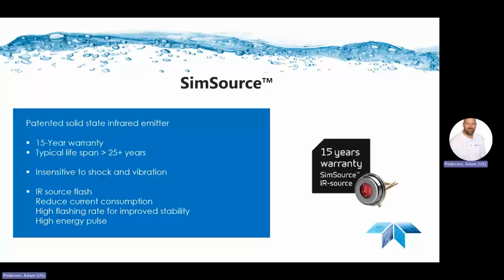The patented SimSource solid-state IR light source is extremely stable. The intensity of the IR light does not deteriorate over time like a filament. Therefore, the GD10 never requires calibration for compensation of this signal. So in addition to the stability, the SimSource light has the best longevity in the industry and is covered by a 15-year full replacement warranty. And the typical lifespan of this unit can last anywhere over 25 years in some instances.